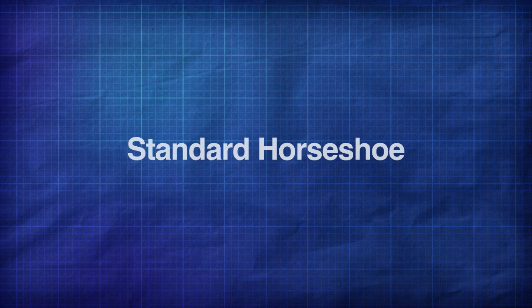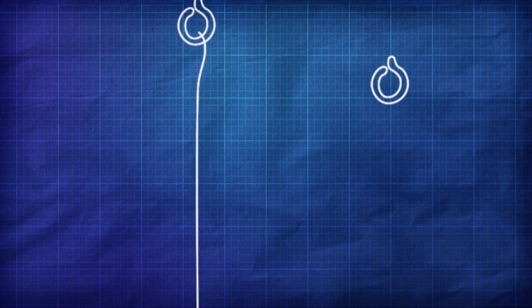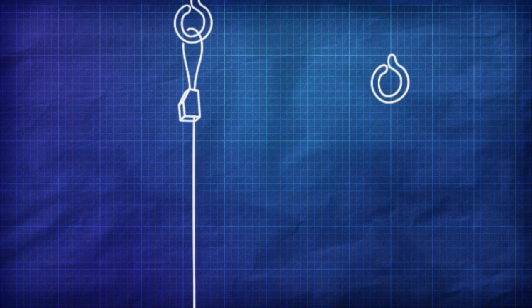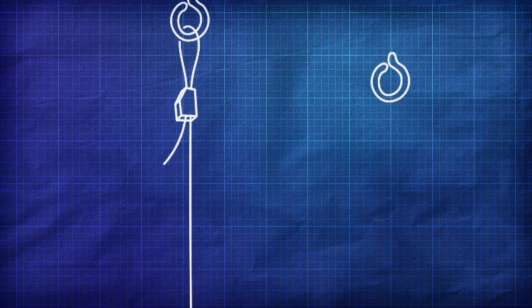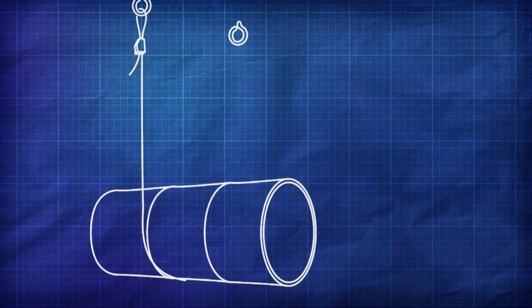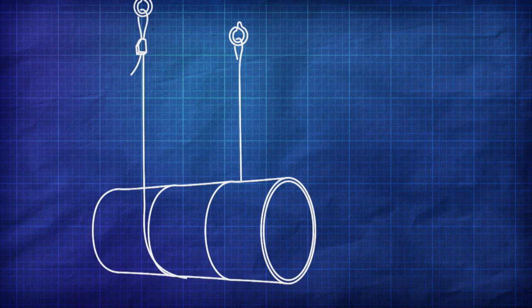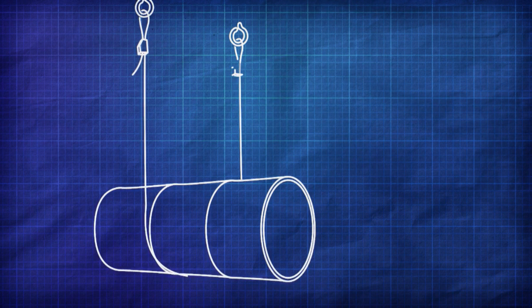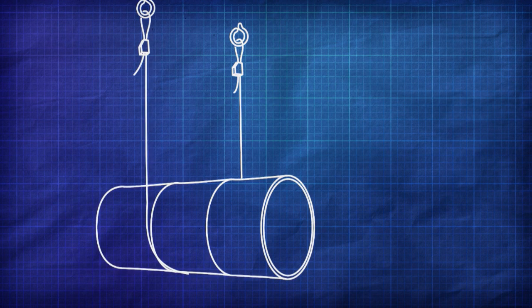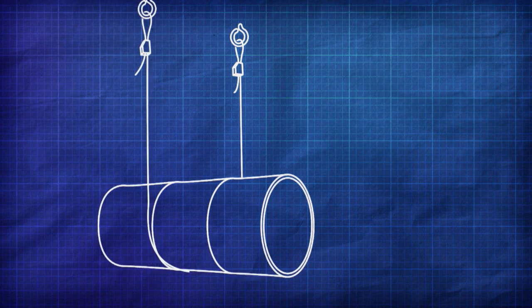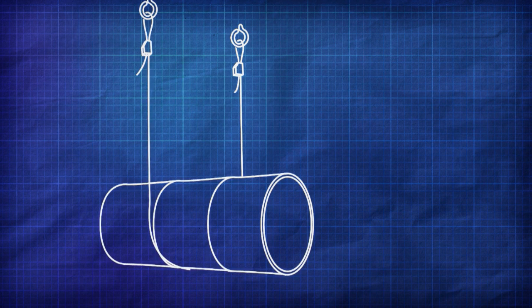The second configuration is the standard horseshoe. Using this method, the steel cable is looped around the upper support and secured with a clutcher mechanism at a 90-degree angle. The cable is then routed under the ductwork and back up to the upper support to be secured, again at a 90-degree angle, with another clutcher mechanism. This configuration is ideal for general-purpose hanging and can eliminate some swinging of the ductwork. When supported in this fashion, the tension in the steel cable is reduced by half. This mechanical advantage is the same concept that makes a block and tackle work.